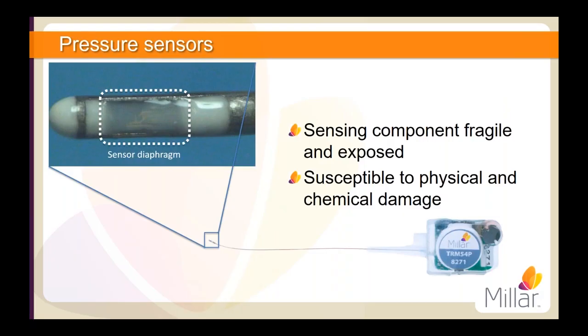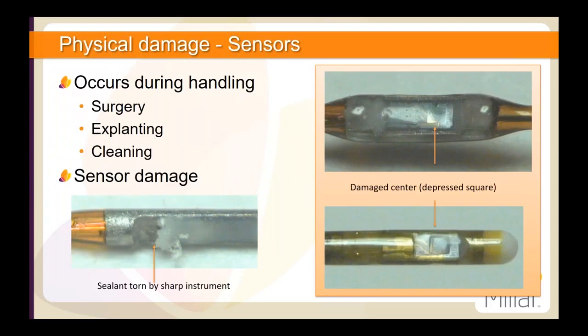On the side of the tip of each pressure catheter, there is the sensor window, shown here. This contains the sensor diaphragm under a thin layer of sealing material. It is flexion of this sensor diaphragm with applied pressure that allows us to measure pressure so accurately. We do need to be mindful, however, that the sensor can be broken if put under too much stress, and the sealing material will fail if punctured or torn. It is also important to consider the effect of any chemicals on these materials.